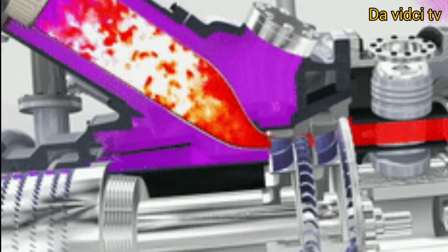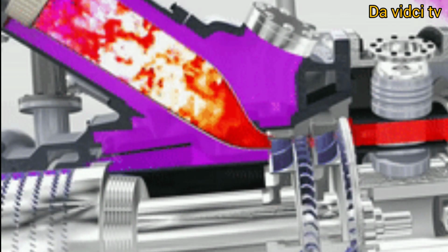Working principle of a gas turbine. The working of a gas turbine is based on the thermodynamic Brayton cycle. The Brayton cycle consists of two adiabatic work transfers and two constant pressure heat transfer processes. The gas undergoes an isentropic, adiabatic compression in state 1 to state 2. This process increases the temperature, pressure, and density of the gas. Next, heat is added at constant pressure in state 2 to state 3. For a gas turbine, a combustion process adds heat.